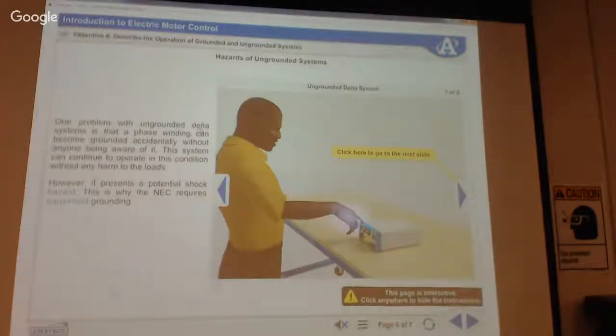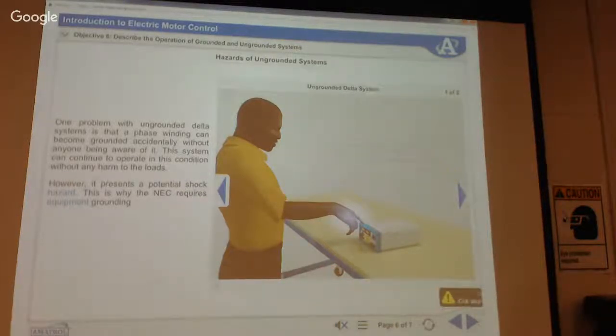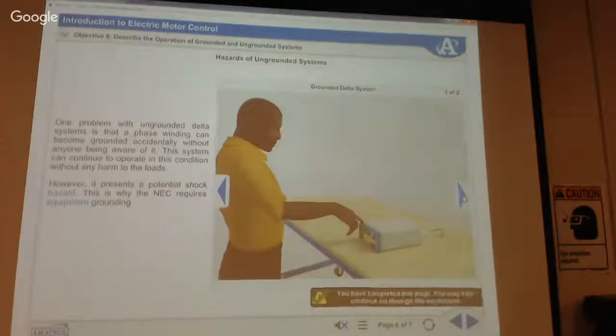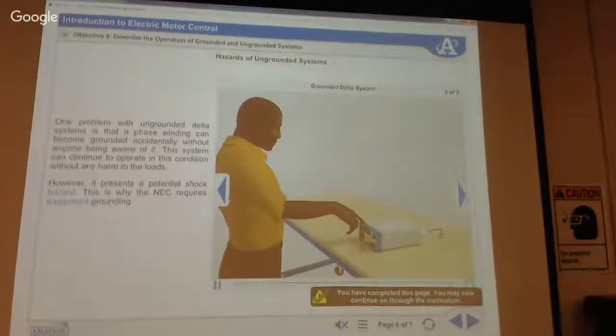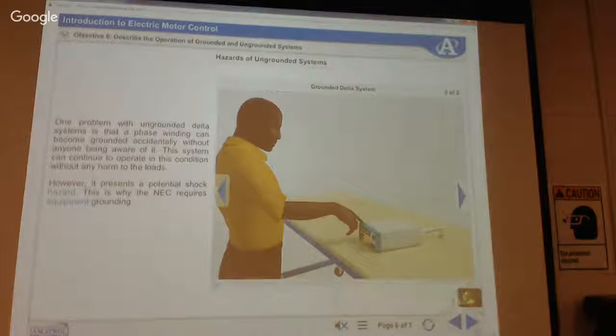One problem with ungrounded delta systems is that a phase winding can become grounded accidentally without anyone being aware of it, and this can result in somebody getting shocked. If we ground it, see, here's ungrounded, here's grounded, he's not getting shocked. The current is going to follow the path of least resistance.